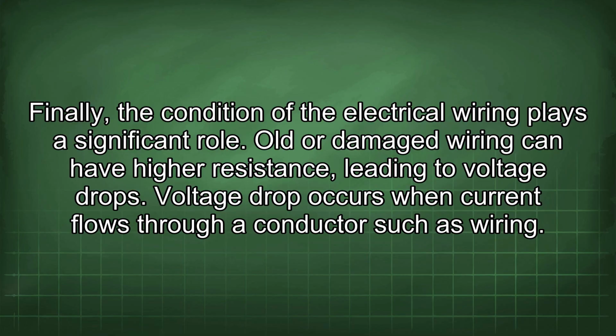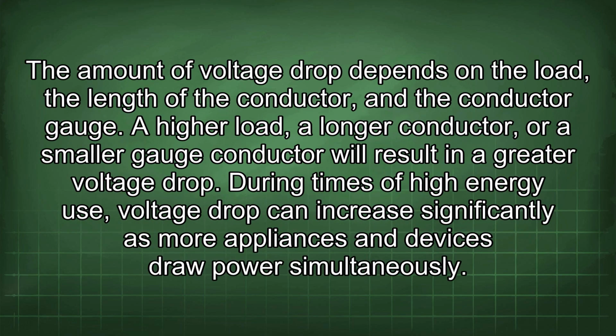Voltage drop occurs when current flows through a conductor such as wiring. The amount of voltage drop depends on the load, the length of the conductor, and the conductor gauge. A higher load, a longer conductor, or a smaller gauge conductor will result in a greater voltage drop. During times of high energy use, voltage drop can increase significantly as more appliances and devices draw power simultaneously.